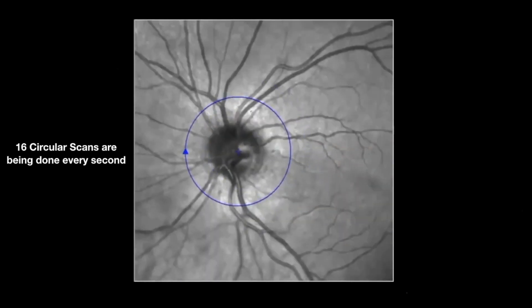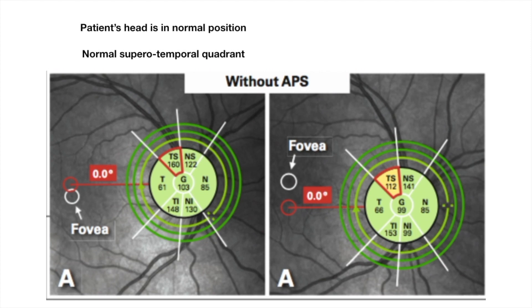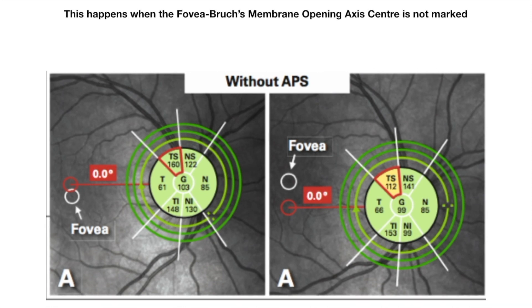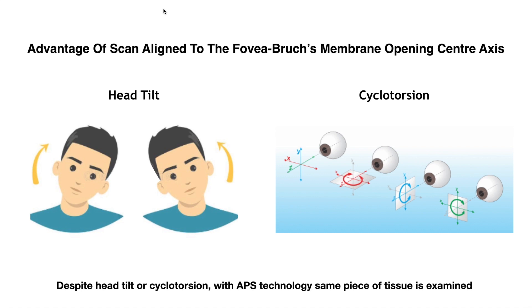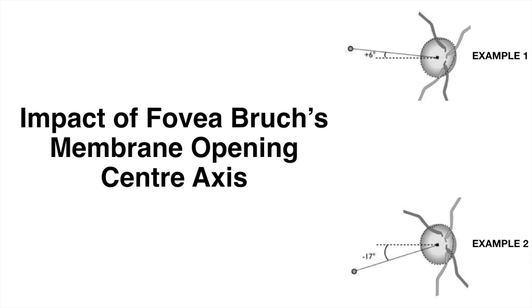16 circular scans are performed every second, and every circle must match the optic nerve head, automatically correcting for eye movement. Without APS, the patient's superior temporal quadrant of the ONH appears normal in normal head position but appears thinned if the head is tilted. With APS technology, the fovea-BMO axis is plotted, compensating for head tilt and cyclotorsion, so the superior temporal quadrant remains the same regardless of head tilt.